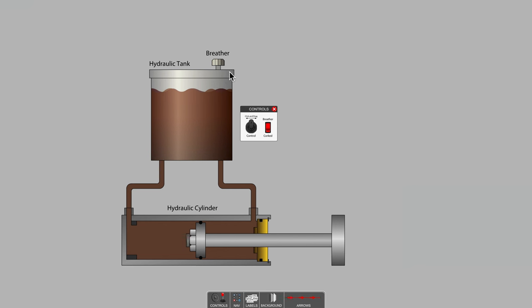What happens in our ability to extend and retract a hydraulic cylinder if contaminants plug the breather? Well, let's just simulate a plugged breather by putting a cork in it. There we go. We've corked our breather port on the top of the tank.